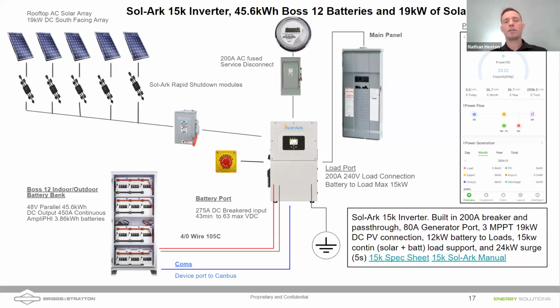Having a battery system allows you to keep that solar power going with AC coupled solar. And the AC coupled solar and DC coupled solar on the Sol-Ark are independent of each other. So you can bring in 19 kilowatts of DC coupled solar, and you can bring in up to 19.2 kilowatts of AC coupled solar. Depending on the size of your battery bank, though, you might want to limit the amount of AC coupled solar you bring in through the Sol-Ark.